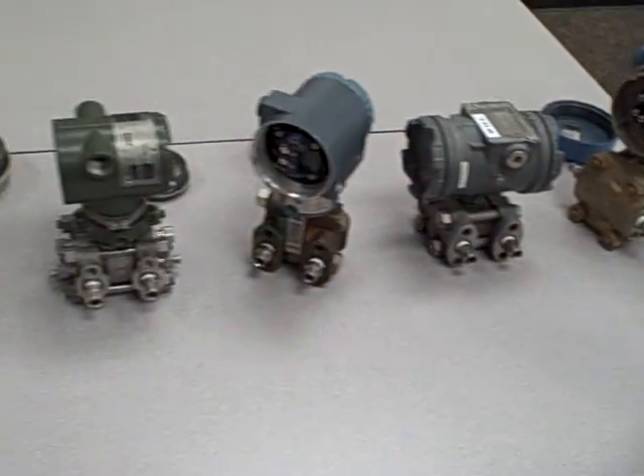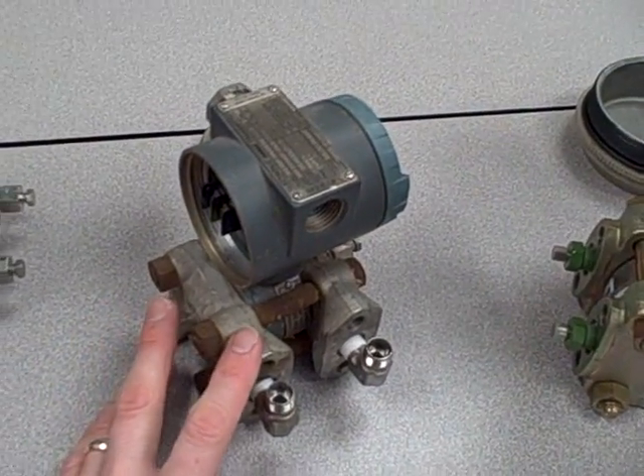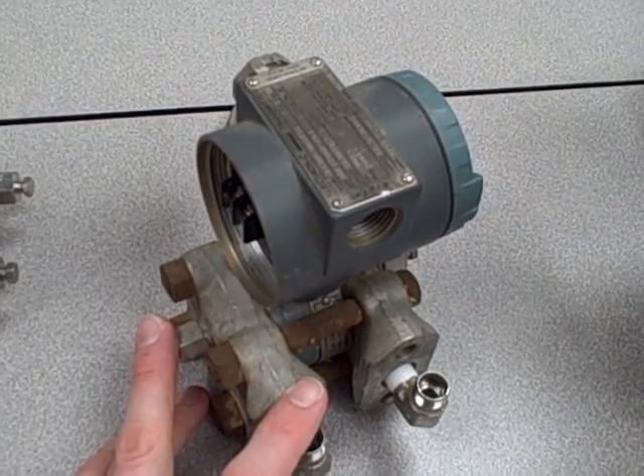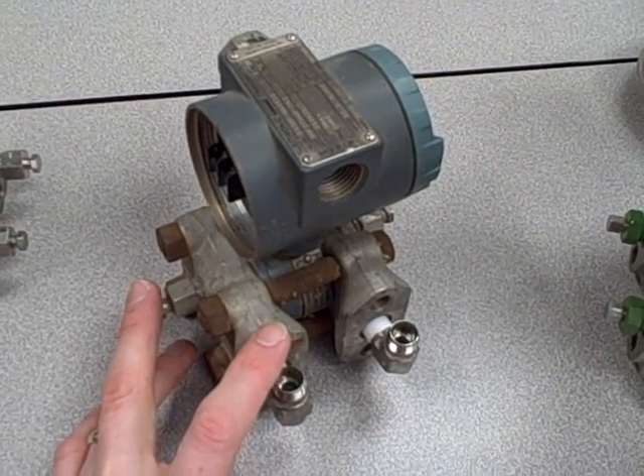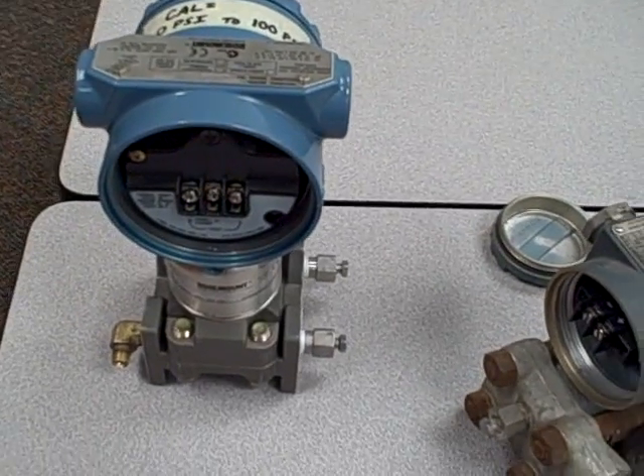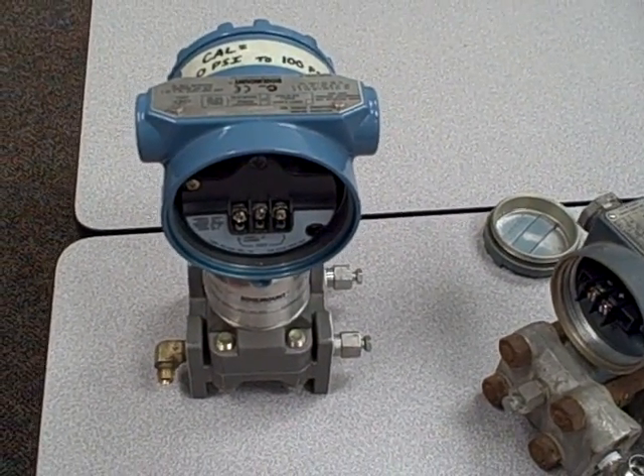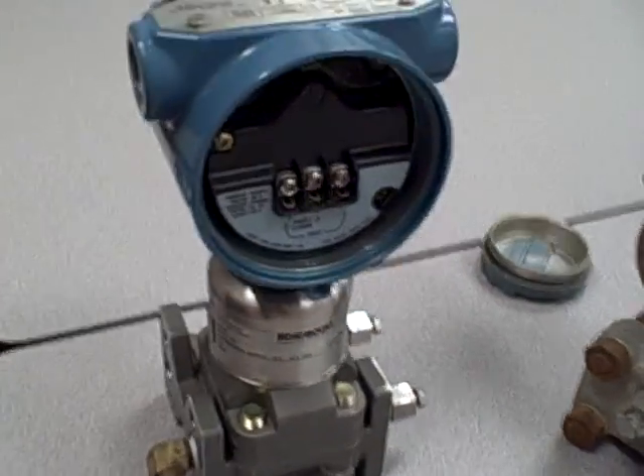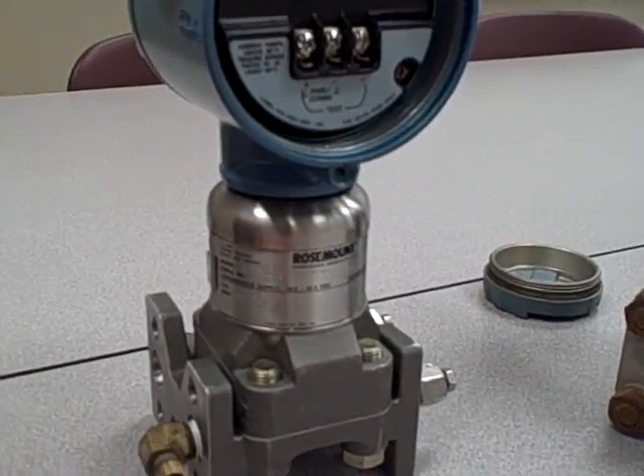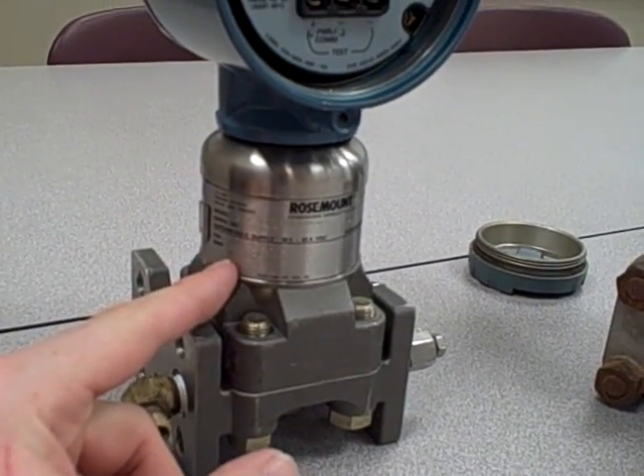As I said before, these transmitters differ in capabilities. Just to give you an example, this Foxboro Model 843 right here is a completely analog unit — all analog electronics inside. On the other hand, right next to it, the Rosemount 3051S is what we call a smart transmitter. It has digital electronics built inside, which can characterize the properties of the cell and correct for nonlinearities in its measurement range.